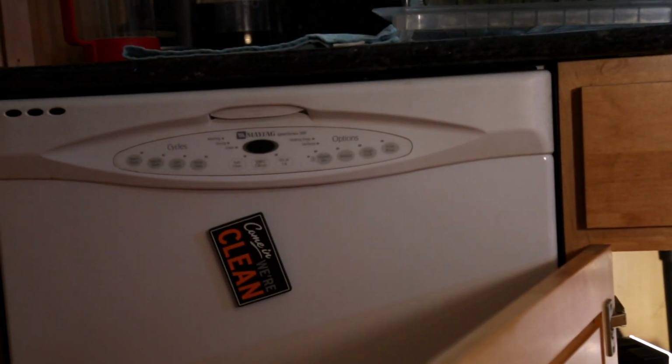And it goes to the dishwasher because the dishwasher is connected to the electrical system through its power cord, and that's grounded, and the grounding hooks up to the frame of the dishwasher, which touches the water piping, and so we have a complete circuit, and the current flow can be going through the dishwasher and then back to the power company by way of the ground lead on the dishwasher.